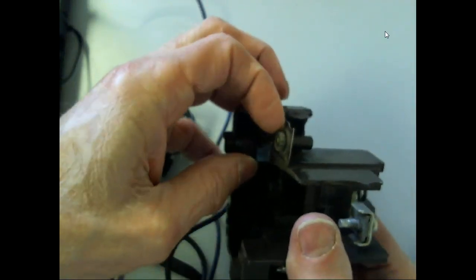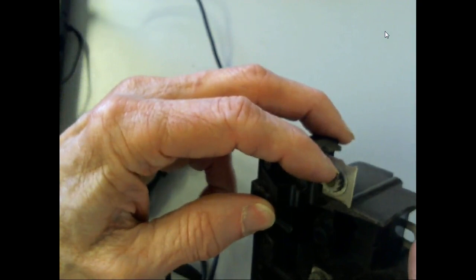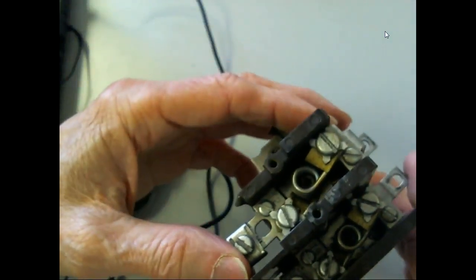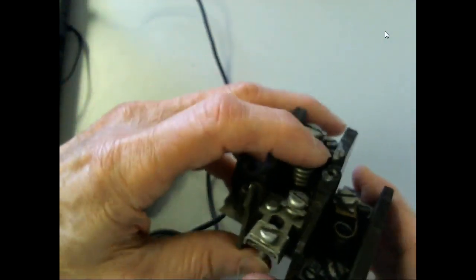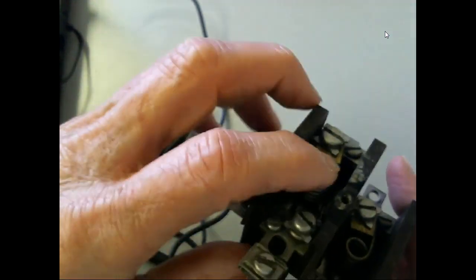And what we have down here is a little ratchet assembly, and we've got a finger over here that's pushing against that ratchet, trying to slip. And when it slips, it's going to kick the overload contact. So the current through the motor runs through the heating coils. The heating coils, if they get too hot, melt the solder. The solder turns into a liquid and lets that wheel at the bottom spin, and that's what kicks the overload. So this is actually the overload sensing assembly that came off of one of these motor starters. Somebody dropped it and broke it.